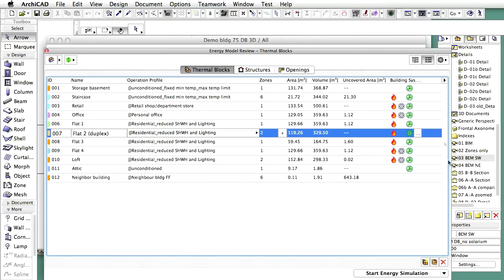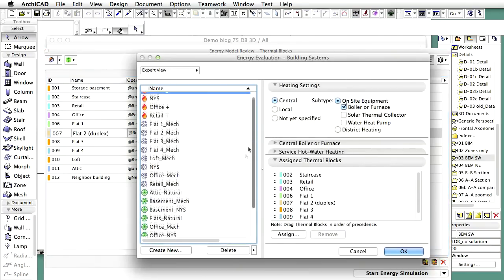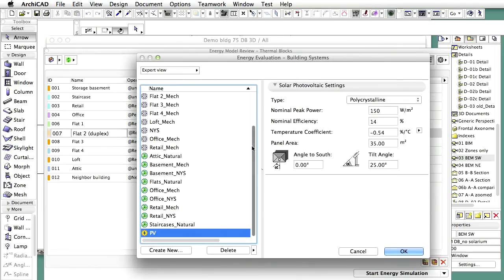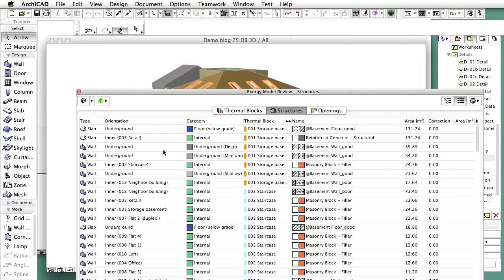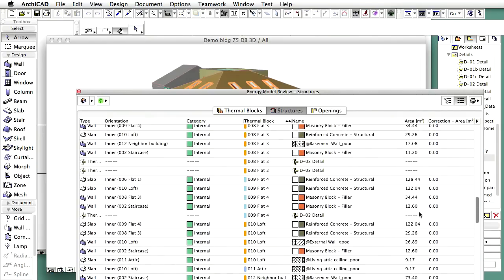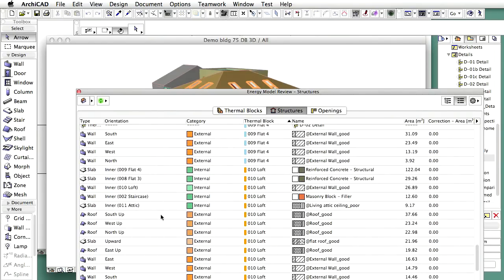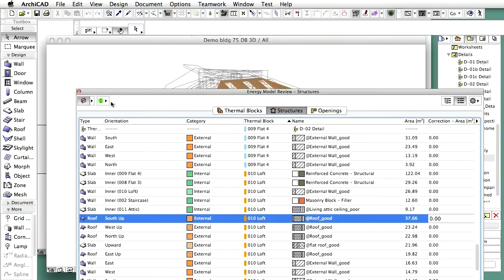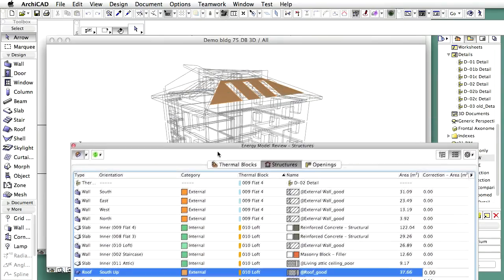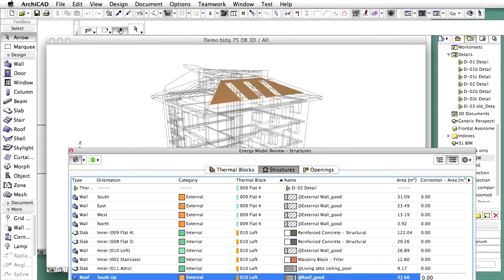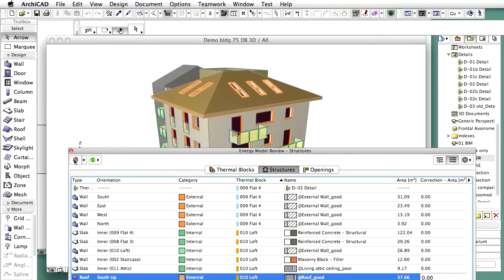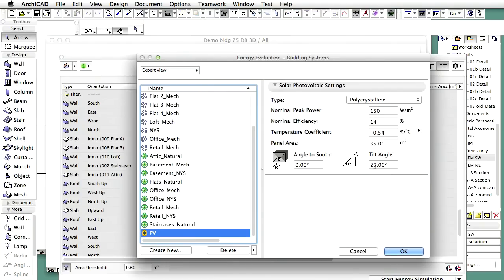In order to produce electricity from a renewable source on site, a photovoltaic system is also defined for the designed building project version. The panels are located on the pitched roof surfaces facing the equator. Display the Structures page of the Energy Model Review Palette and select the southern pitched roof to determine the available space for the PV panels — its area is a bit more than 35 square meters or 375 square feet. The area and inclination of the installed polycrystalline photovoltaic panels correspond with the area and inclination of the equator-facing pitched roof.